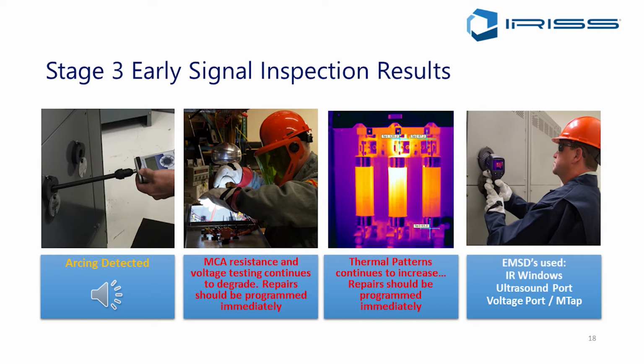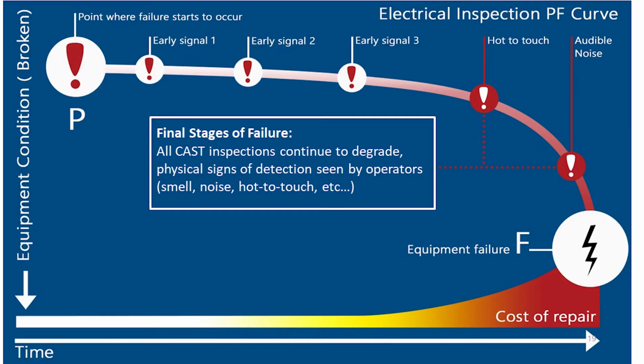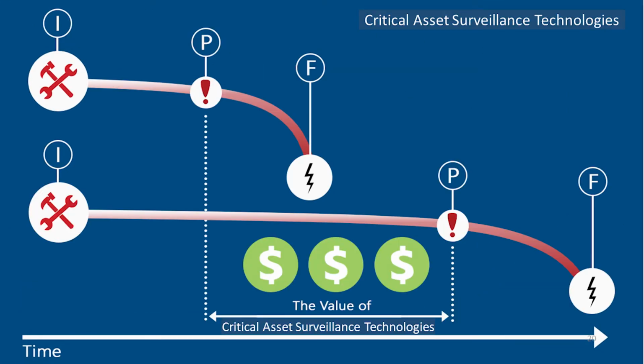We might see that motor current—we're now seeing a couple of parameters that are in the red zone, so we need to take some corrective action there. So again, all of these are early warning signs, and the value of any type of condition-based maintenance program is that we get to reset the P-F curve. If we find the problem and decide it's now time to take corrective action, we get to reset the P-F curve and put that equipment back into mint condition again. Now we start all over and begin monitoring again.